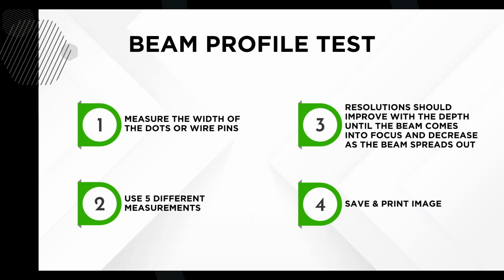Let's click that out. And what you should see on this particular one, we took 4 measurements. We'll do one more. And what you should see is from 1 to 4, you should see it start wider and come in as the beam comes through. You should see it start wide and then come into play more, and then again widen back out as the beam comes through. That is what they're looking for there.